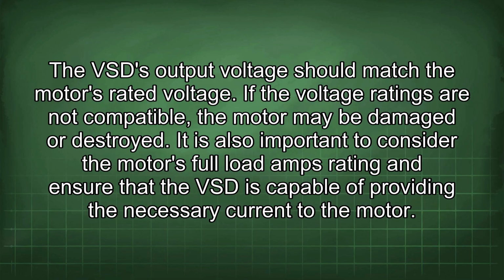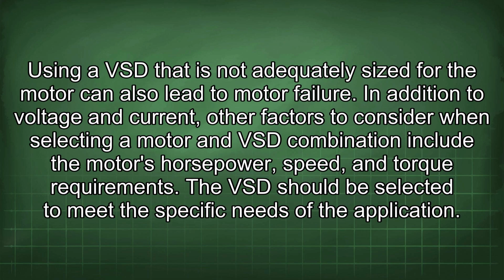It is also important to consider the motor's full load amps rating and ensure that the VSD is capable of providing the necessary current to the motor. Using a VSD that is not adequately sized for the motor can also lead to motor failure. In addition to voltage and current, other factors to consider when selecting a motor and VSD combination include the motor's horsepower, speed, and torque requirements. The VSD should be selected to meet the specific needs of the application.